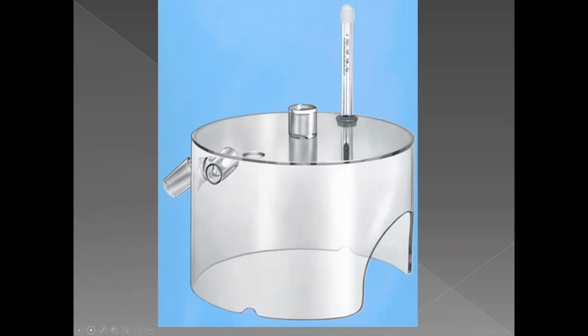If you have to analyze the FiO2 you're delivering, you analyze inside the hood. Not outside or not in line, like you don't put the analyzer and the tubing outside of the hood, you have to put it on the inside.